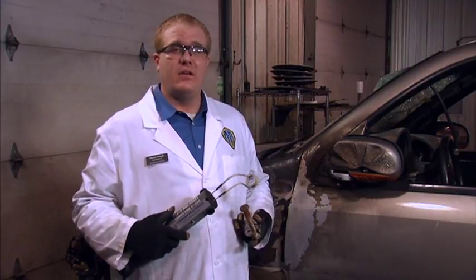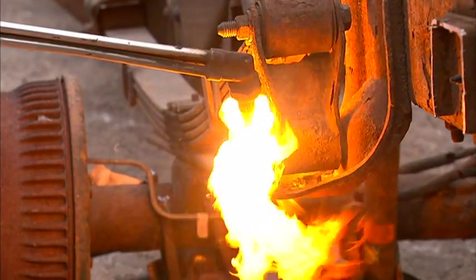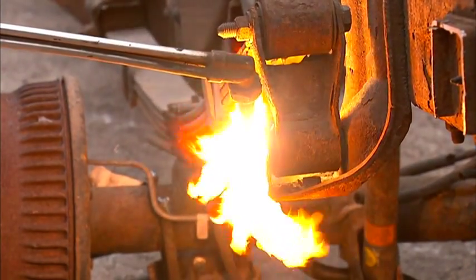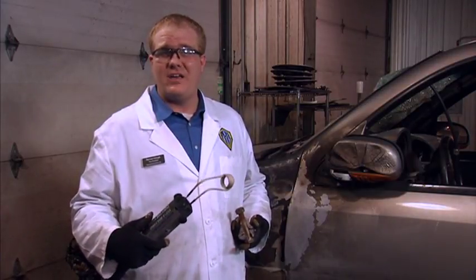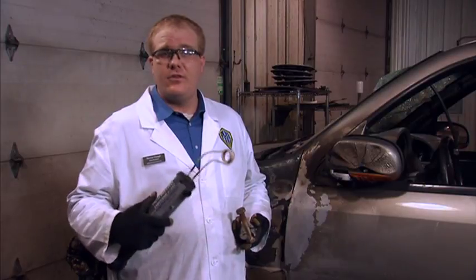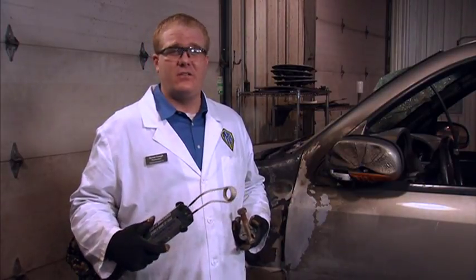Seized, frozen, rusted, or thread-lock compound bonds can often call for other means of nut and/or bolt removal. Though a torch can effectively work, it will more likely cause collateral damage. So we're going to use the U555 attachment to create a flameless and precise heat on the nut. The U555 can heat any size nut or bolt up to 4 inches and sometimes larger.